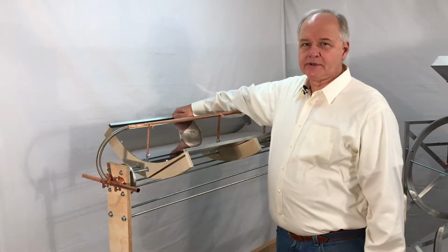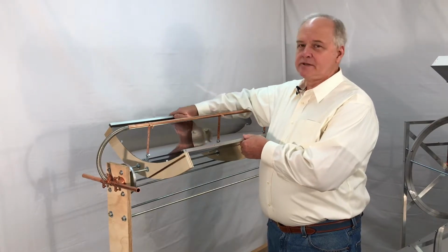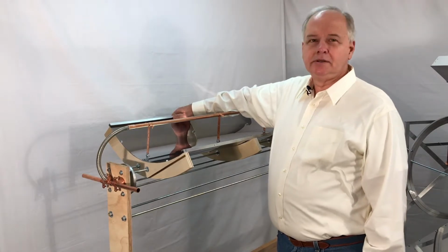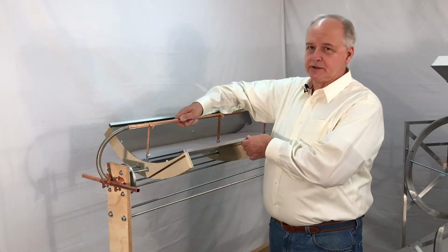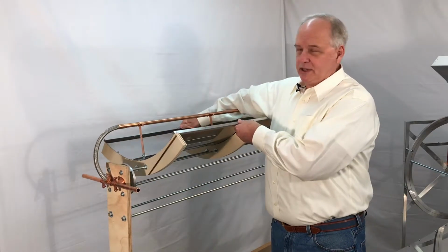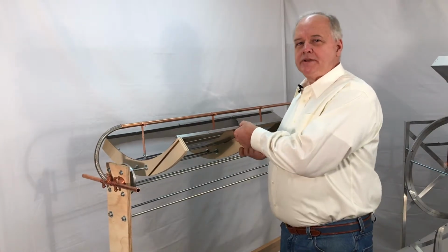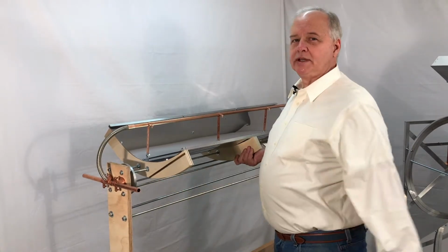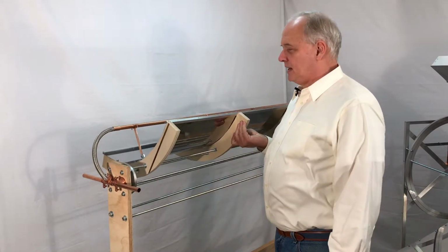All parabolic troughs reflect sunlight onto the focal line. There are dozens of variations worldwide of mirror structure and size, but they all have the same relationship of the parabola to the collector tube. The rotation of the trough occurs under the parabola. This places the collector tube about 6 feet away from the rotation point, causing the collector tube to travel in a slow arc as the trough follows the sun throughout the day.